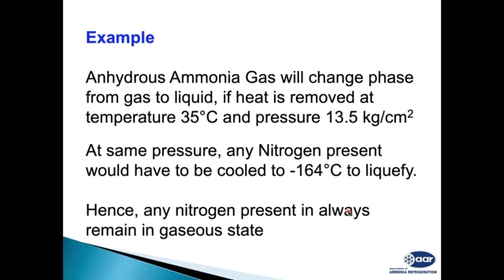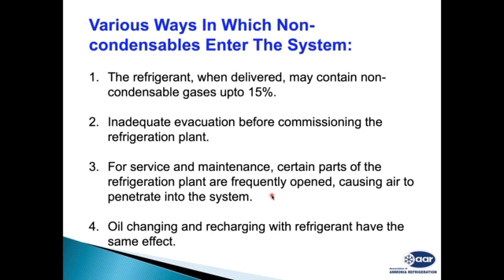So for example, if we have ammonia at 35 degrees C, the pressure is around 13.5 kg per centimeter square. But at the same pressure, nitrogen would require -164 degrees centigrade to liquefy. So if nitrogen is present in our refrigeration system, it will always remain in the gaseous state, and any gas remaining in the gaseous state on the evaporator side will not generate any positive refrigeration effect. What happens with this air or nitrogen or other gases, we'll see further. Let's see how it comes into our system.